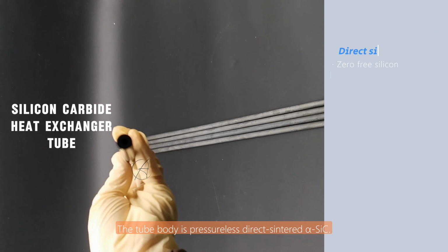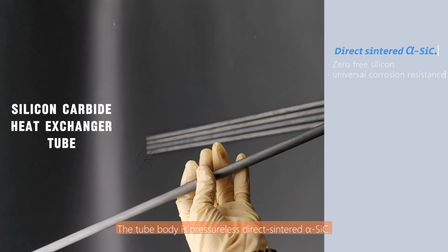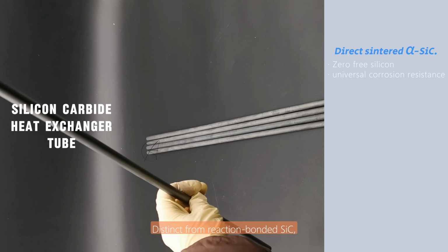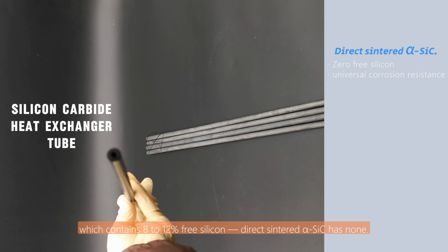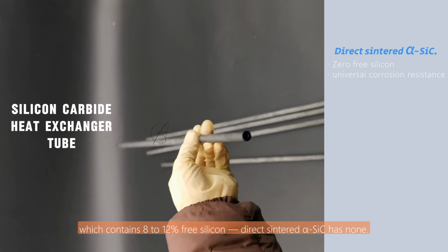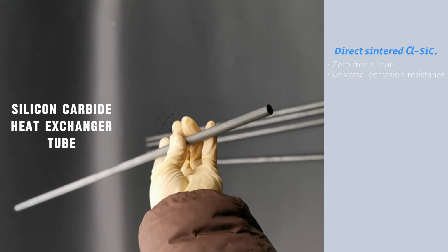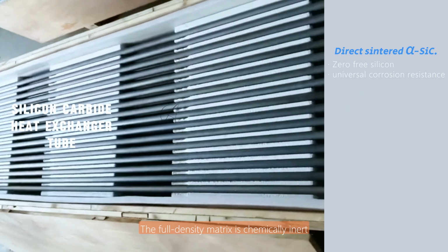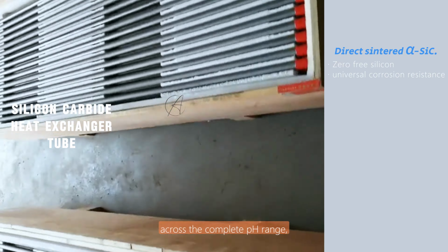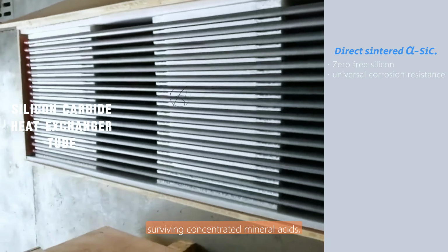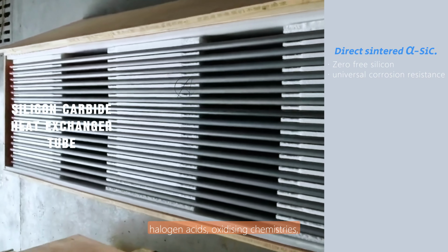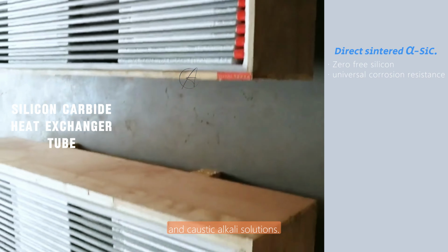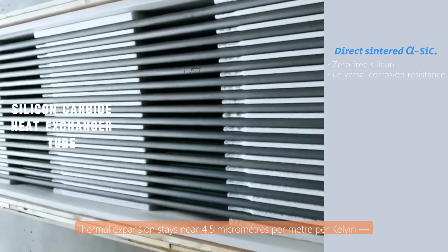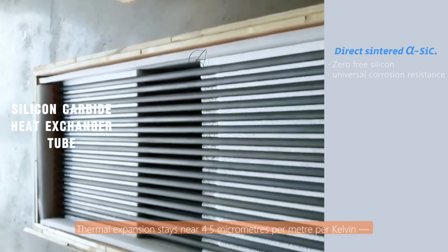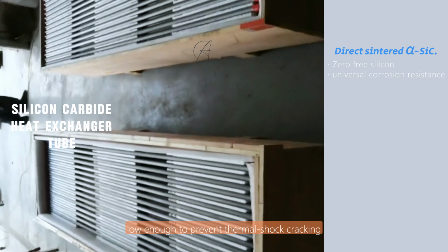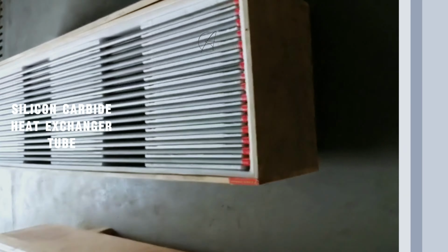The tube body is pressureless direct-sintered alpha silicon carbide. Distinct from reaction-bonded silicon carbide, which contains 8 to 12% free silicon, direct-sintered alpha silicon carbide has none. The full-density matrix is chemically inert across the complete pH range, surviving concentrated mineral acids, halogen acids, oxidizing chemistries, and caustic alkali solutions. Thermal expansion stays near 4.5 micrometers per meter per Kelvin, low enough to prevent thermal shock cracking under rapid temperature swings.